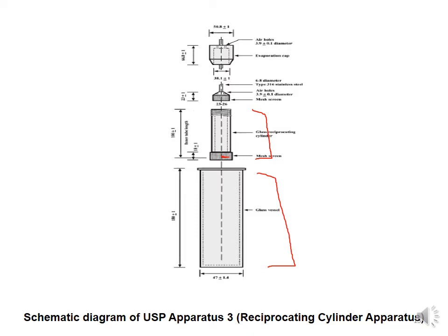The vessels are partially immersed in a suitable water bath of any convenient size that permits holding the temperature at 37 Celsius degrees during the test. No part of the assembly, including the environment in which the assembly is placed, contributes significant motion, agitation, or vibration beyond that due to the smooth vertically reciprocating cylinder.